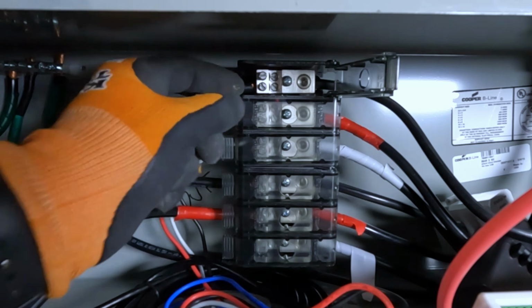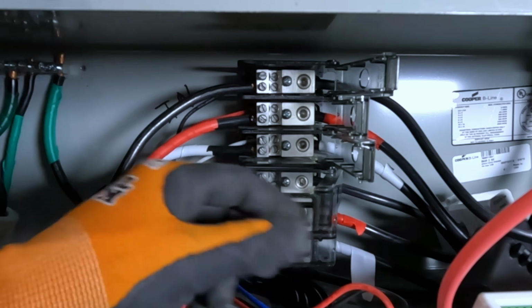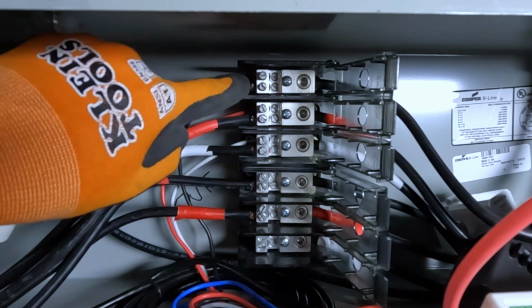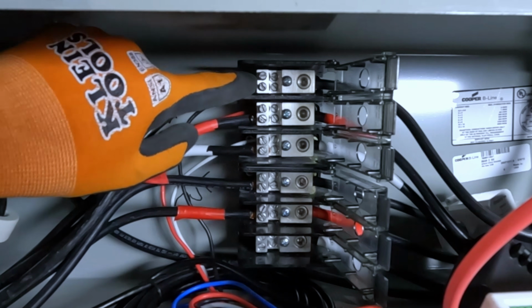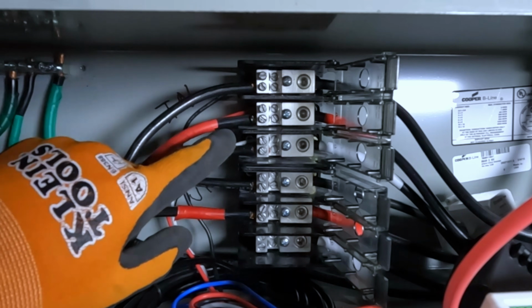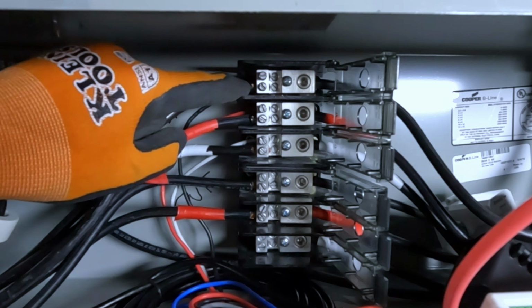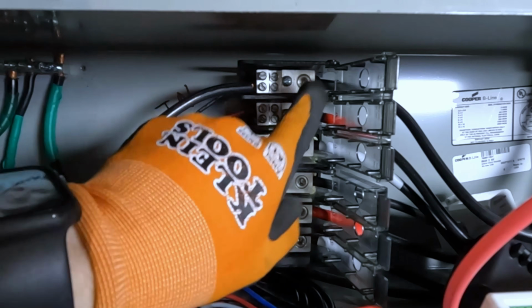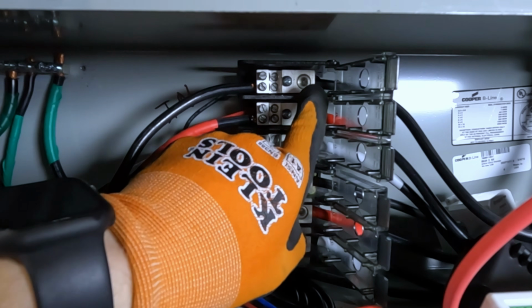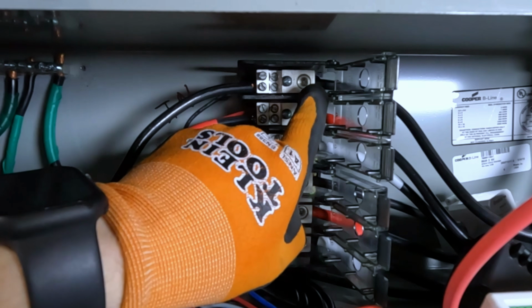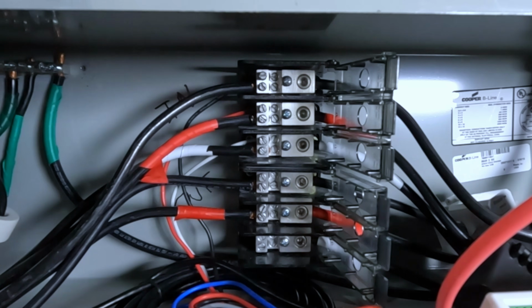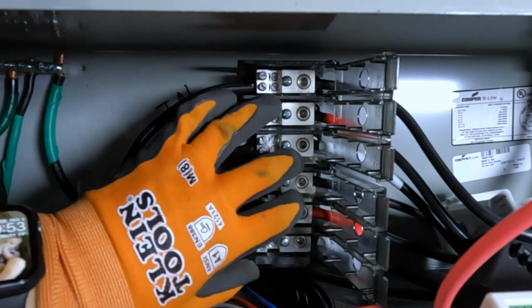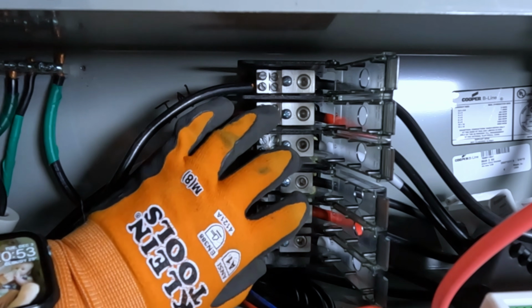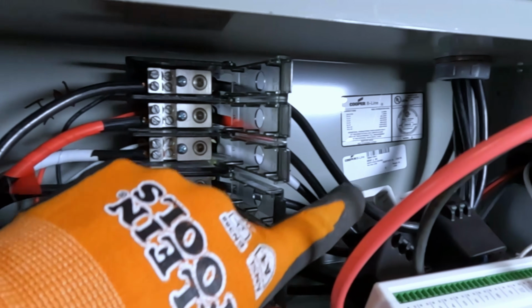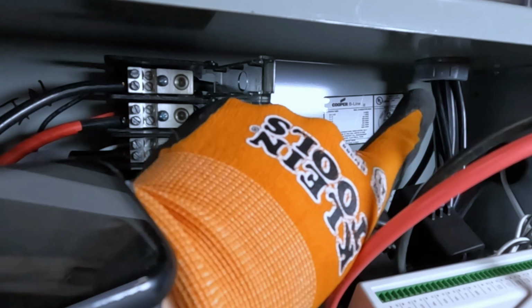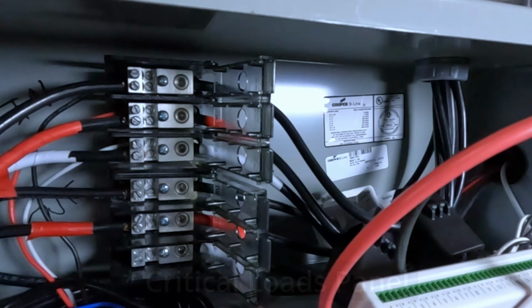So if I open the covers, there's 4 terminal points on the left side and 1 on the right hand side. We can put from 4 gauge to 14 gauge on this side, and we can have from 2/0 to 14 gauge on this side. And this way I only have to deal with my connections here, and I only have to run 1 set of cables up that conduit to my combiner box.